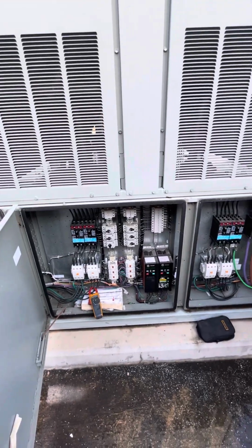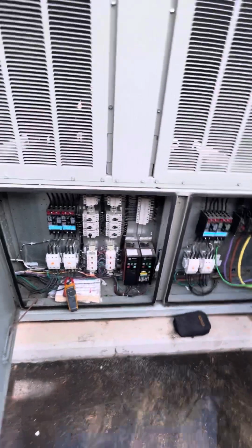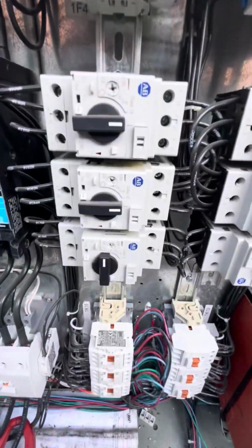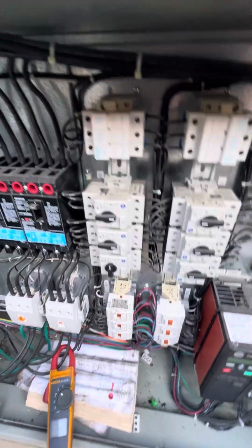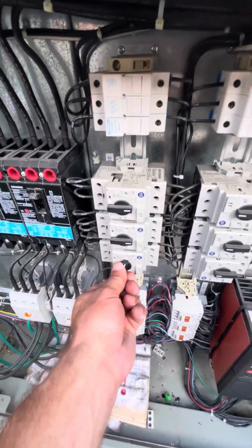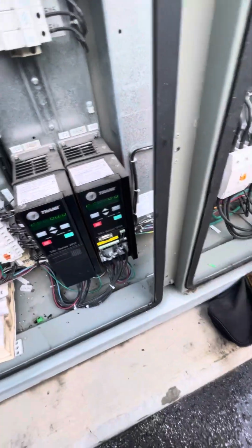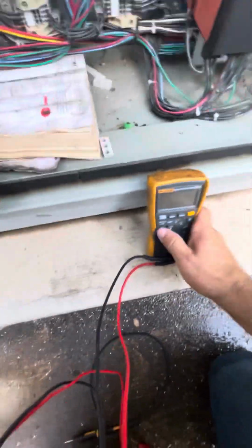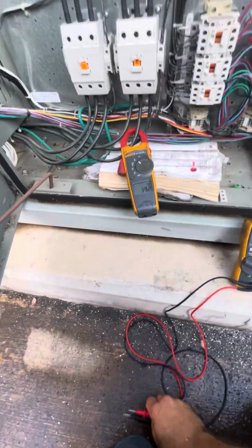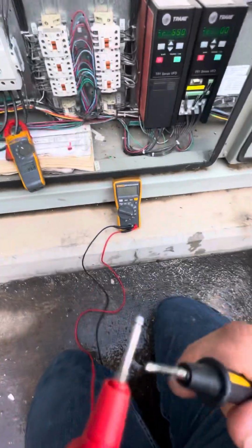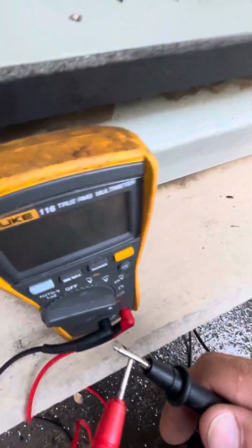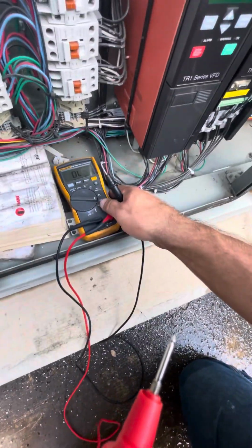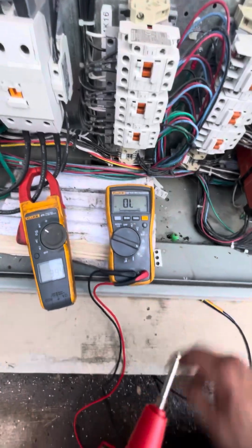So the issue we had was on our initial assessment, we noticed that this breaker was tripped. It's obviously not in the trip position, so the trip position is halfway like that. But I shut it off, wanted to do some testing through the wiring. And what we're doing here is just a tone test. We're checking resistance, checking meter leads like so. Get a sound from the old meter. This is a Fluke 116 true RMS meter. It's a pretty good meter.